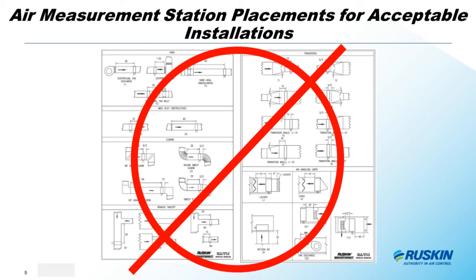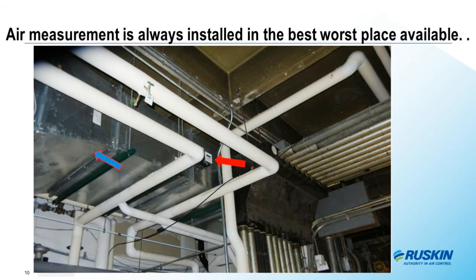The red arrow in this photo shows the air measurement station in the duct where it could be installed just downstream from the blue arrow, which is the transition from the duct silencer. Sorry, but this is not an ideal location, but it is the best location available. We've always stated that the greatest feature of the electronic air measurement product is that probes can be installed almost anywhere. And the worst thing is that they are installed almost anywhere. Again, with more sensing points in the duct, we're making those bad locations better, solving a problem for the industry.